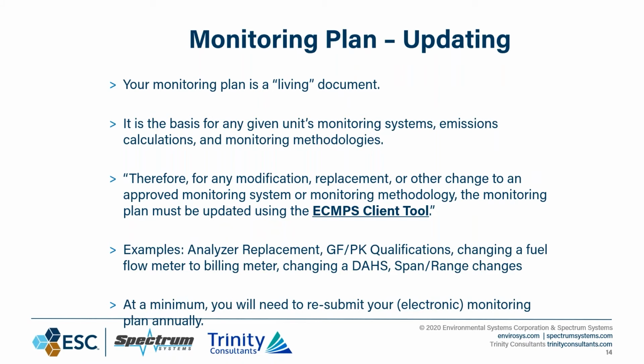Now let's get into updating the monitoring plan. Like Adam was talking about, this is meant to be a dynamic document, a living document. It is the basis for your monitoring systems, your unit's monitoring systems, your emissions calcs, your monitoring methodologies. And as a direct quote, any modification, replacement, or other change to an approved monitoring system or monitoring methodology, the monitoring plan must be updated using ECMPS through the platform.